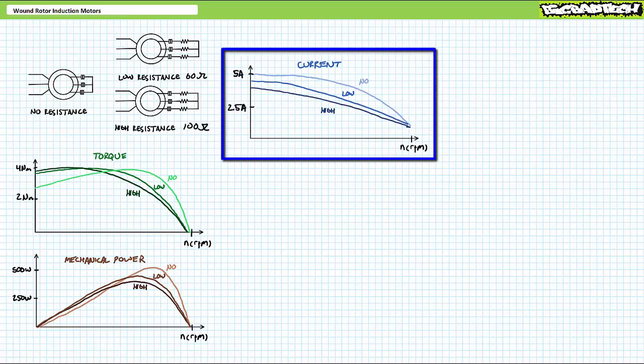Let's now take a look at current for these three configurations. Each configuration demonstrates the motor draws a small amount of current in the no load condition, which increases as the motor moves to the rated condition, transitions to overload conditions, and eventually flatlines. The high resistance configuration draws less current and the no resistance configuration draws more, with the low resistance configuration straddling the difference. This makes perfect sense: a high resistance rotor is known to demand less inrush at start, thus it draws less current.